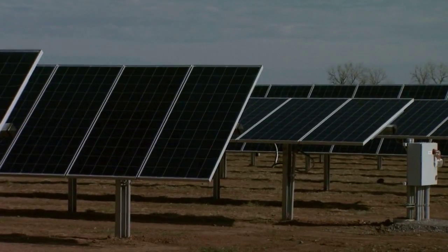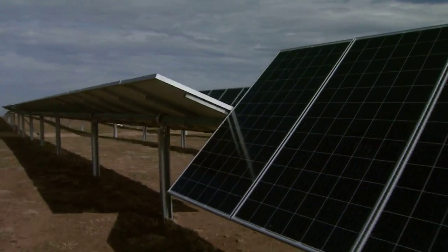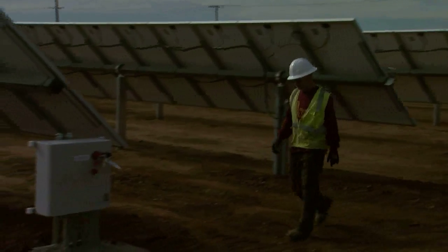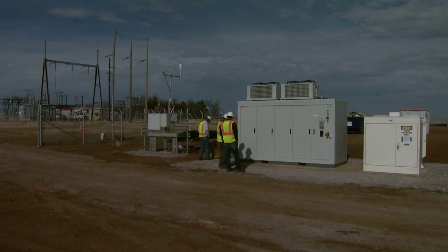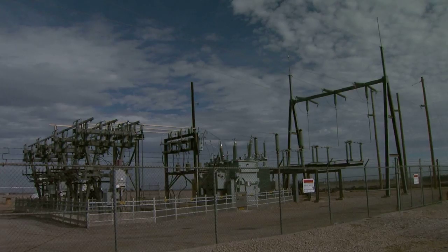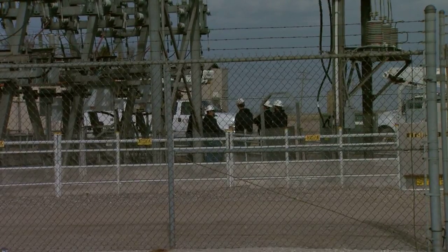The Tuttle farm is a single-axis tracker — it follows the path of the sun from sunup to sundown. Each section of panels is connected in series to boost their power and feed energy into a collector box. From there, the electricity flows to an inverter where it is converted from DC to AC and then into the substation, where the voltage is stepped up to match the power flowing through the main distribution line.